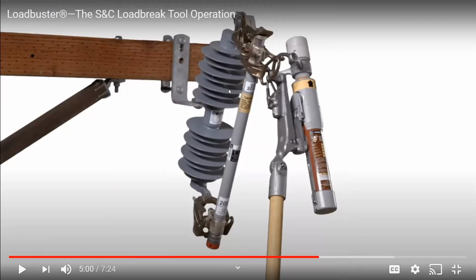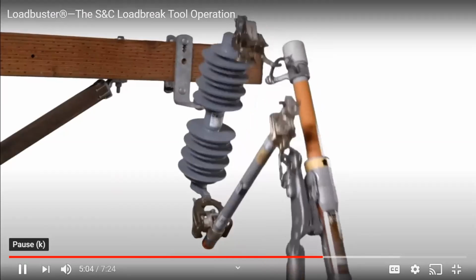Okay, so you hear what he said? What minor arcing? You might see it spitting a little bit and spitting a little fire out of this area and this area. And also it's got exhaust ports here and here where it breaks the load, and it's going to expel all the gases that come off that load break. So just be ready for it. Now, if you're breaking a small load with it, that's not going to happen. But if you're reaching towards the rating of the tool, 600 amps and that nature for this one, it's going to make a little noise. It's going to make a little bit of fire up here. The only sound will be that of the load buster tool tripping.